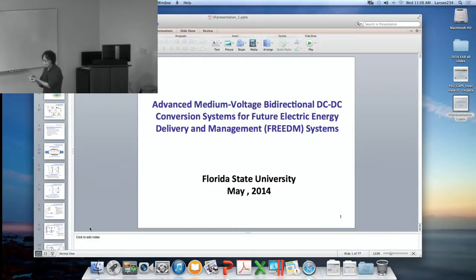But we found that if you design the battery based on 2.5 times the peak load, for bus 205, the cost is minimum. And for each bus, since the load power is different, the battery size is different.